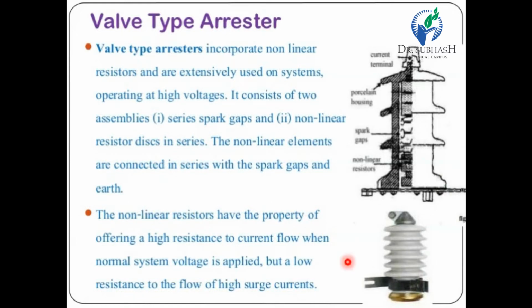Now the valve type arrestor. Valve type arrestors incorporate non-linear resistors and are extensively used on systems operating at high voltages. It consists of two assemblies, series spark gaps and non-linear resistor discs in series. In this figure, in the middle there are spark gaps, and below the spark gaps there are non-linear resistors, and the spark gaps and non-linear resistors are connected in series. The non-linear elements are connected in series with the spark gaps and earth. So the lower end of the non-linear resistor is connected to earth.